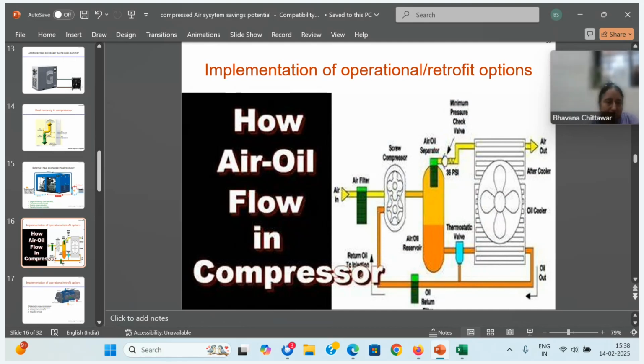See, most of the screw compressors available in the market are of two types. Basically, it is single stage or multi-stage. Then it is oil injected or dry screw compressor. It's called an oil injected type compressor. In oil injected type compressors, air and oil are mixed. Air is sucked, oil is also injected, and both are compressed together and sent to the air oil separator, where air and oil are separated. Air goes to the after cooler and goes out. Hot oil goes to the oil cooler and returns to the system after the oil filter. And there's no pump in a screw compressor. The oil flow happens due to the vacuum created in the compressor and the pressure of the tank.